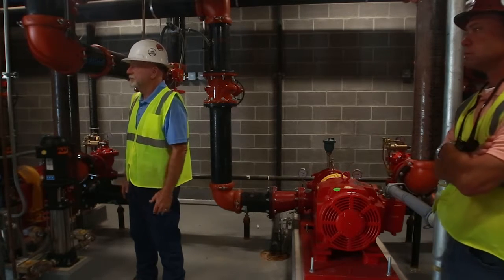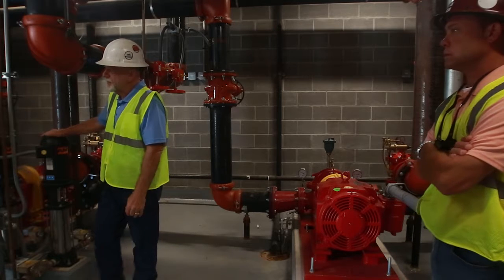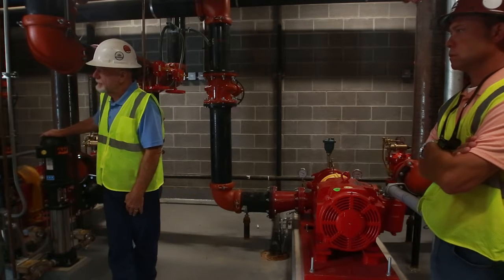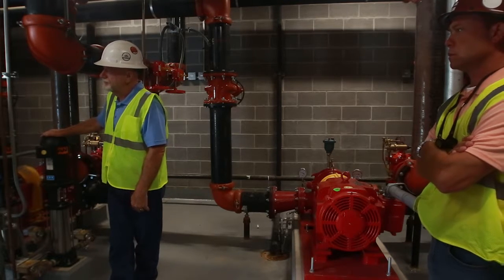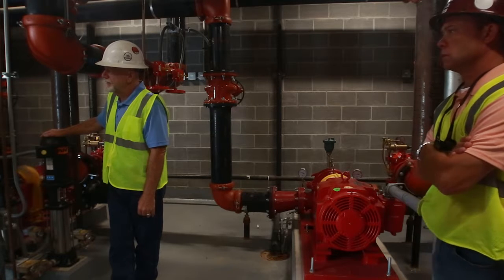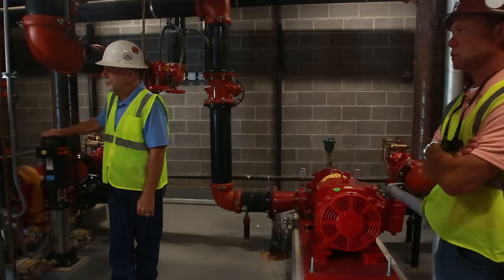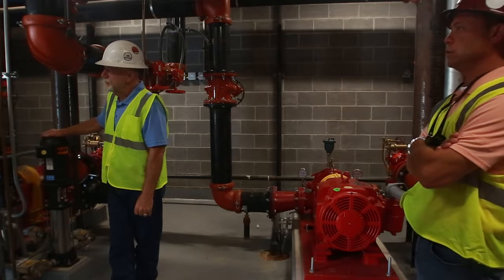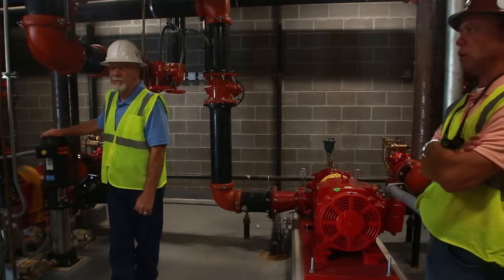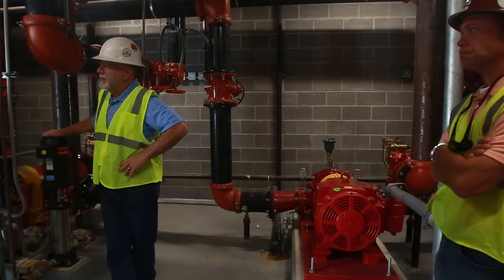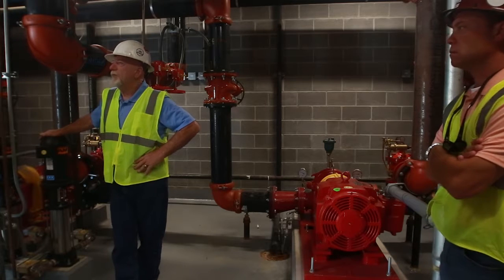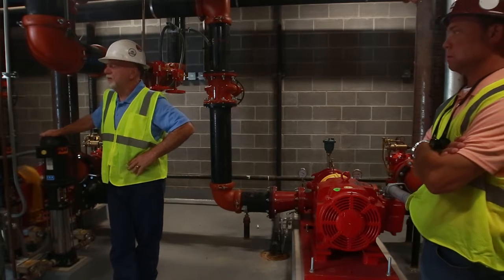Okay, well, when it comes on wide open, sometimes we've got some dry systems, we've had it overpower the valve for the generator system over there because air pressure may be down just a little bit or something. That pump kicks on like that, boom! It trips that dry system and fills that generator room. Okay, well, what identifies that to you that?